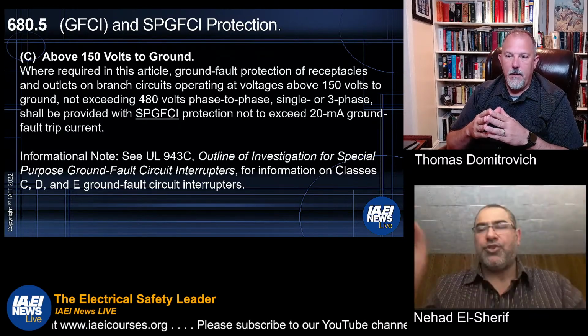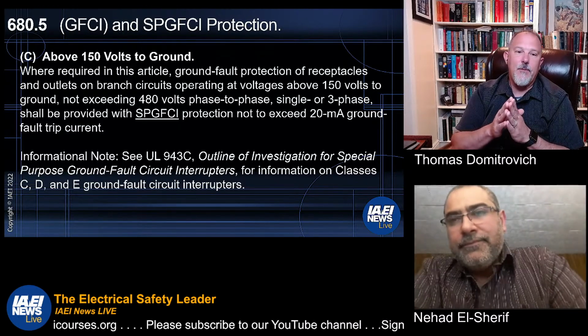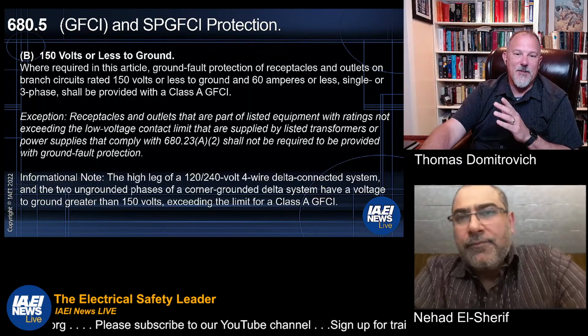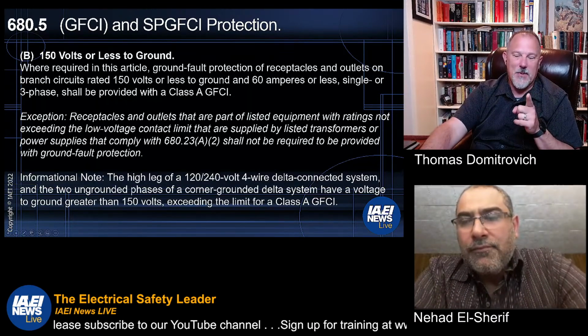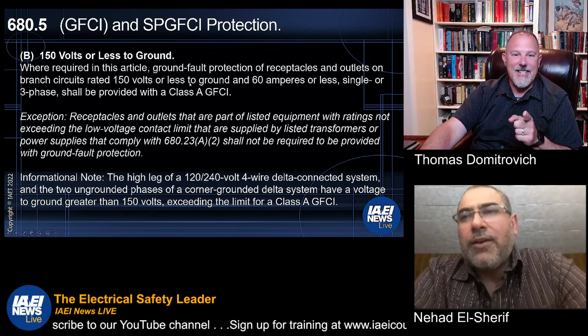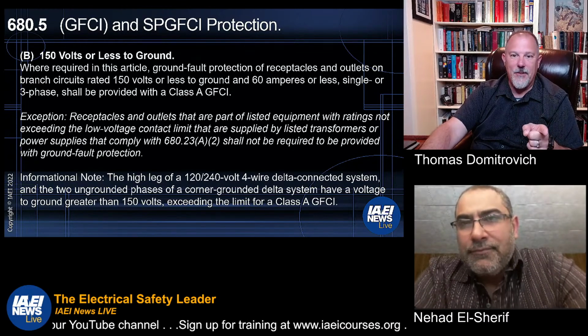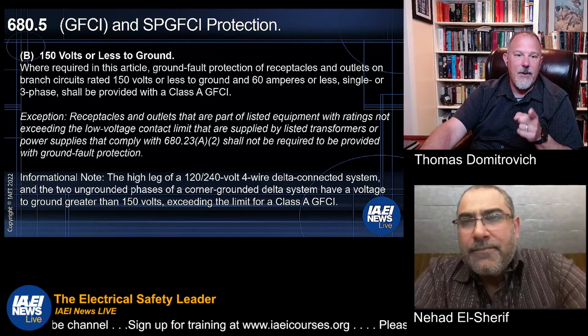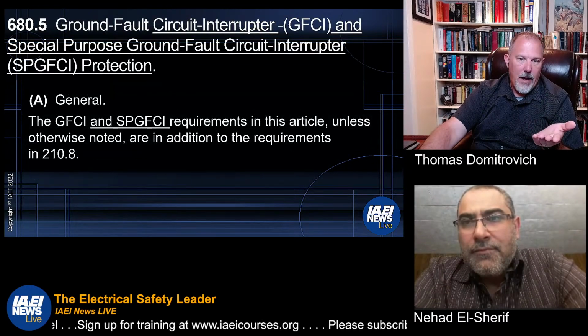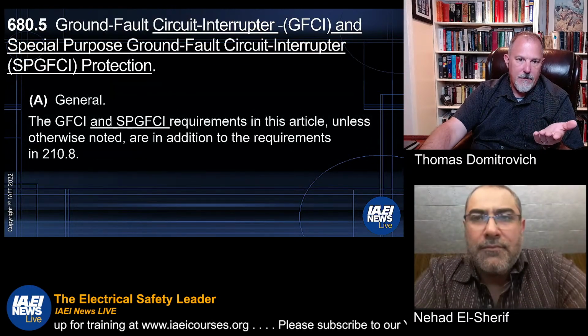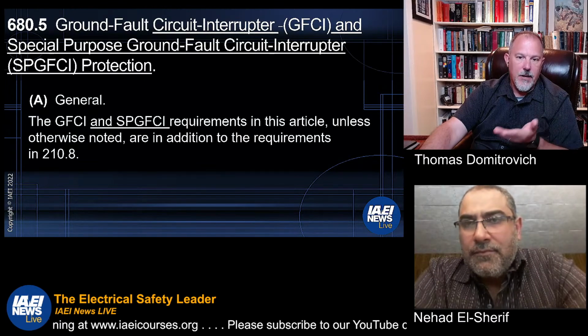So it's kind of the flow chart. Yeah. When I first read this one, I thought it said special purpose, but it's a Class A, and a Class A is 150 volts or less to ground and 60 amps or less. And (A) tells us that it's unless otherwise noted, or in addition to the requirements in 210.8.